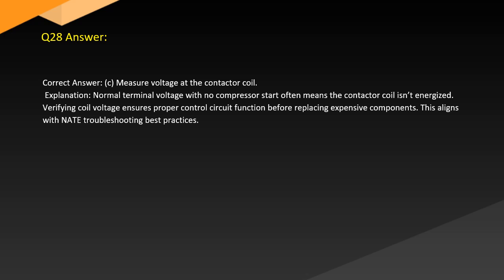Answer. Correct answer: C. Measure voltage at the contactor coil. Explanation. Normal terminal voltage with no compressor start often means the contactor coil isn't energized. Verifying coil voltage ensures proper control circuit function before replacing expensive components. This aligns with NATE troubleshooting best practices.